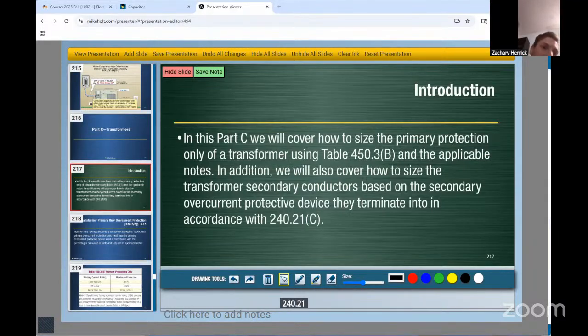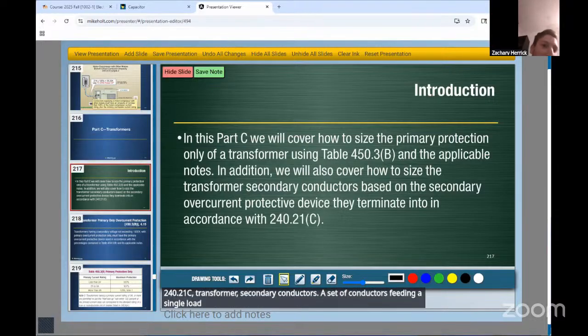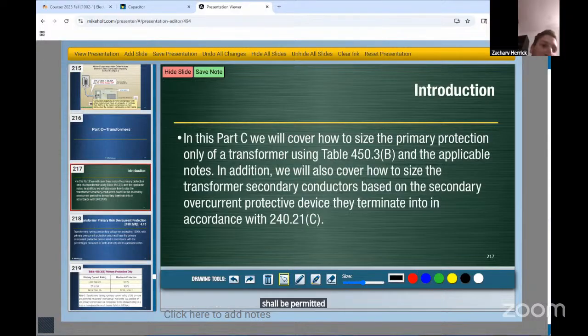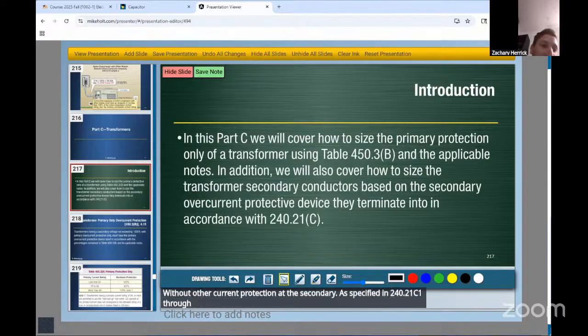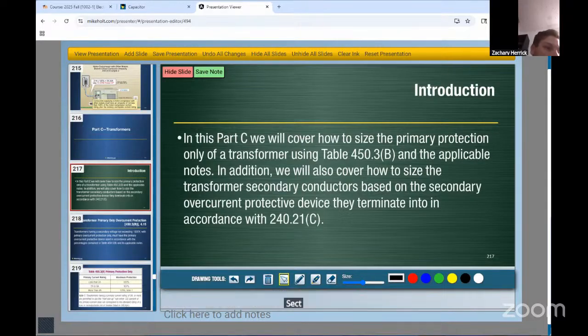240.21(C), transformer secondary conductors. A set of conductors feeding a single load, or each set of conductors feeding separate loads, shall be permitted to be connected to a transformer secondary without overcurrent protection at the secondary, as specified in 240.21(C)(1) through (C)(6). Section 240.21(B) shall not be permitted for transformer secondary conductors.